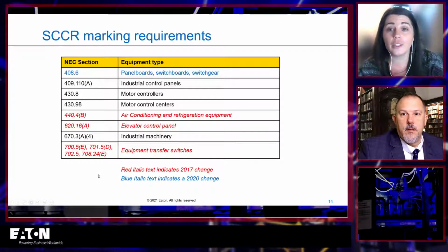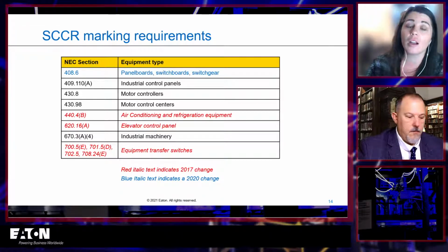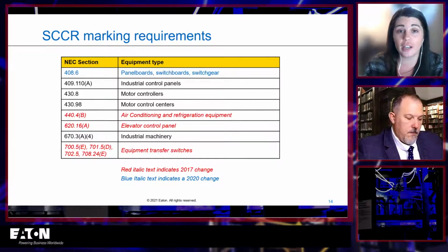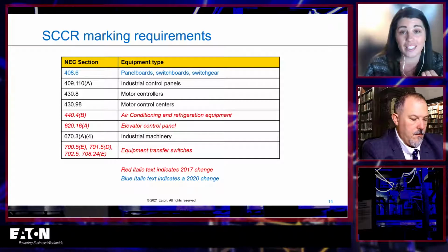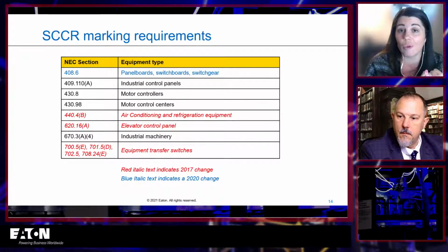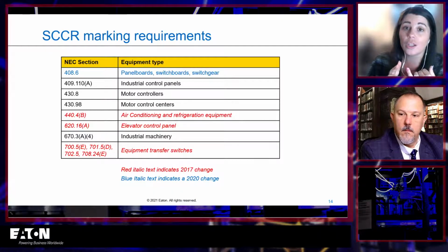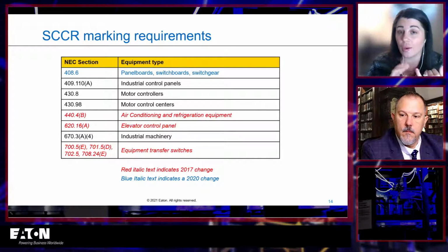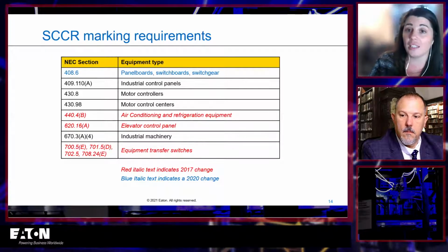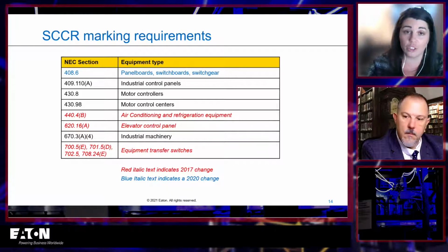So we'll talk a little bit here about the NEC marking requirements for SCCR, and I've included this basically because in 2017 there were a ton of changes or additions made to short circuit current rating in the NEC. So I want to make sure we review what those were, as well as give you a couple of the updates that also occurred in 2020. You'll see it basically just gets more and more important. The NEC is clearly telling us that this is something we have to pay attention to.